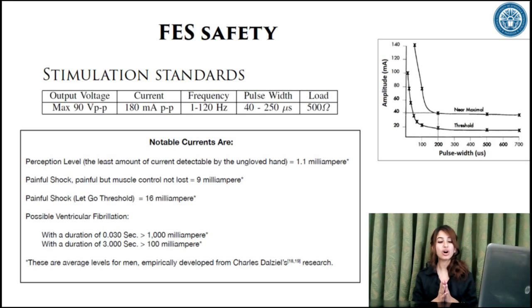Some of the specifications of the FDA approved devices are to be shared with you. The output voltage should be maximum 90 volts peak to peak. The current should be 180 milliamperes peak to peak. The frequency should be 1 to 120 Hz. The pulse width should be 250 microseconds, as I've already told you that it is most optimum. And the load is 500 ohm because the high voltage reduces the resistance of the skin. The curves show a relation of pulse width to the current required for muscle stimulation, using a pulse width of 250 microseconds for optimum stimulation according to research.